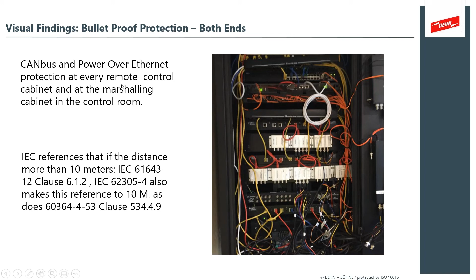Visual finding, bulletproof protection on both ends. It's really important to understand that a surge protection device needs to be installed if the distance between the source and the equipment is more than 10 meters. Significant currents and voltages can develop over that distance, and it's important to have surge protection devices on power over Ethernet and different IO control circuits at both ends. So this is something that we're looking for.